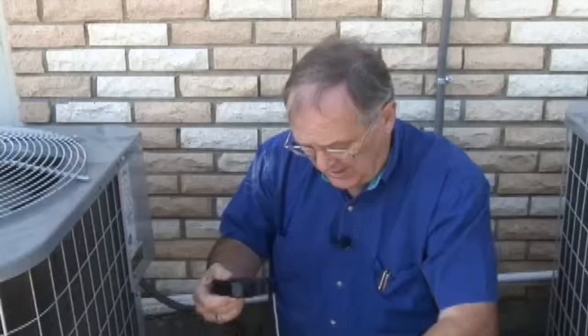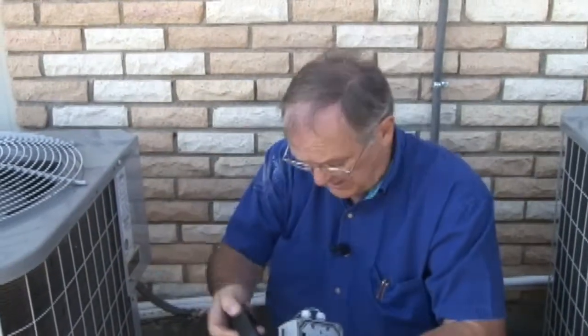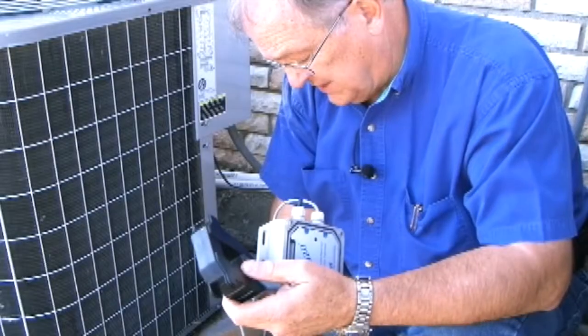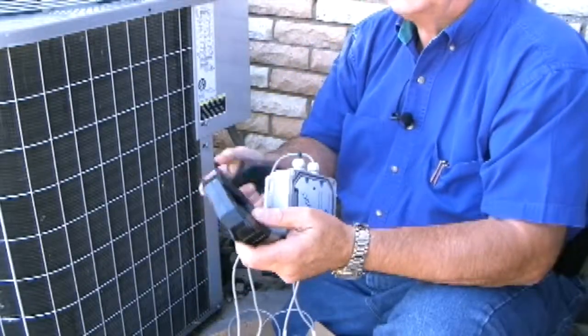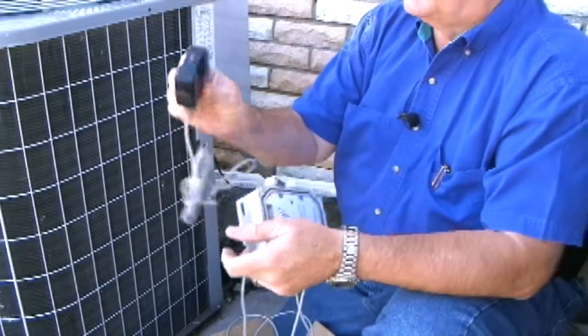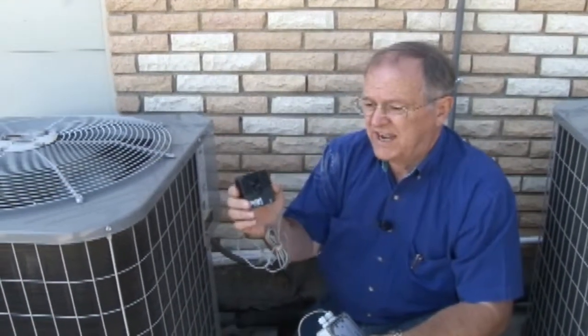You start the data logger using the instructions that came with the software, being careful to set it to record either every 1 minute or every minute and a half. You want to make sure you can collect at least 1 week's worth of data. And obviously the sensor needs to be sized properly. In this case, this Ampere probe is much too large for this particular system, so we would use a smaller Ampere probe. Actually, from the standpoint of accuracy, the larger probes don't read very accurately for a smaller amount of current. So we typically want to use the right size Amp probe.